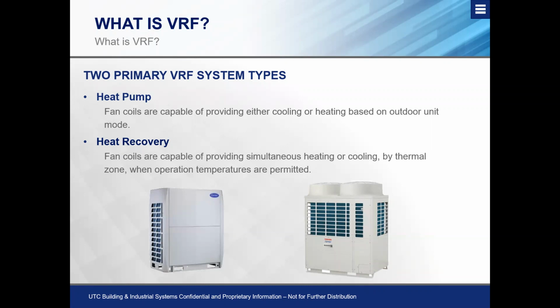Okay, now there are some variances depending on what style of system. For example, our system at the bottom left-hand of the screen, which is the Carrier system, is a two-pipe heat recovery system, which can be a little confusing depending on what you're used to looking at as far as three pipes versus two pipes, which is one of the reasons why I don't like the designation between three-pipe and two-pipe VRF, because it can get confusing on which one's a heat recovery and which one's a heat pump.